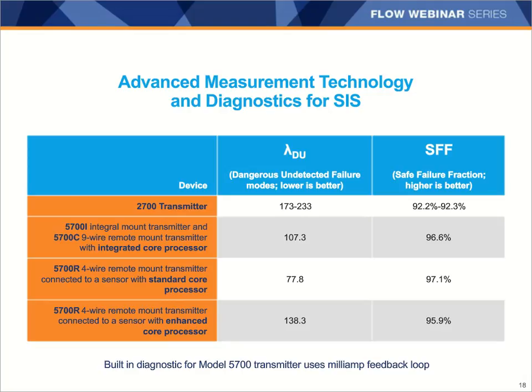The Model 5700 has incorporated a new diagnostic on the SIS version that allows you to continuously monitor the milliamp output of the device with a built-in milliamp input, and this is what has contributed to that higher SFF number. By comparing the expected output with the input value, the meter is able to reduce some of the potential undetected failure modes, and the SFF is improved. More information about this can actually be found in our safety manual on the Model 5700 web page, and a link to that web page is actually located in your resource center.